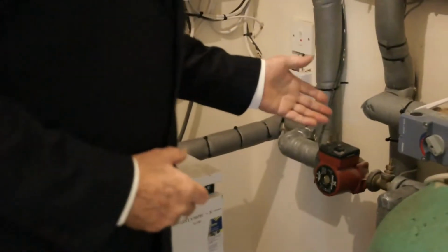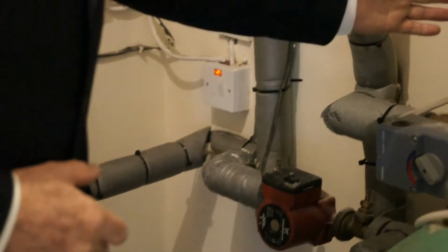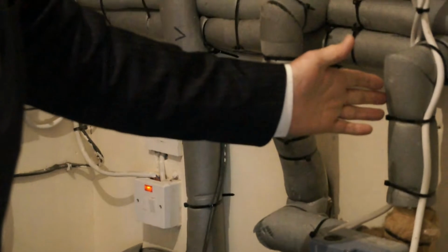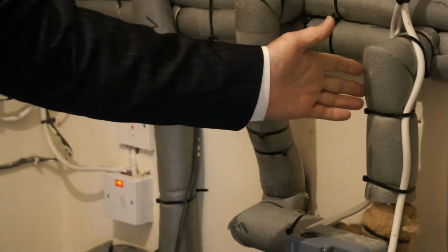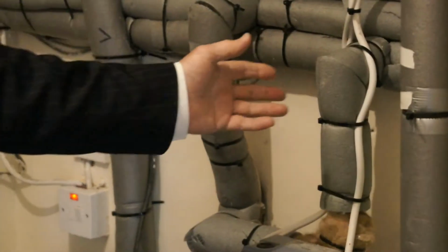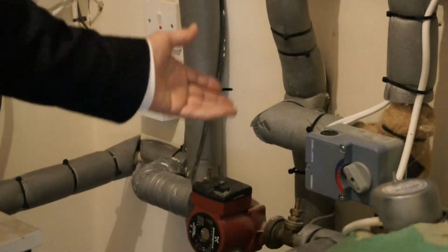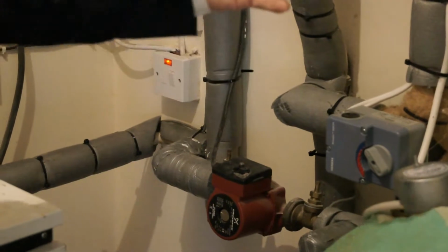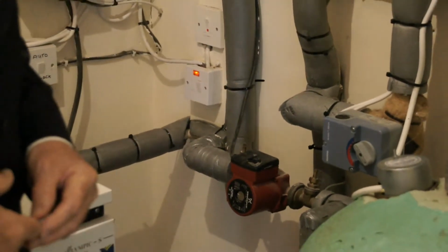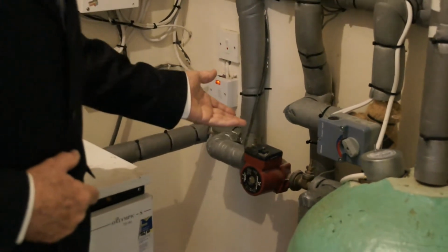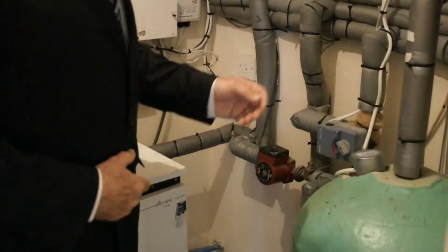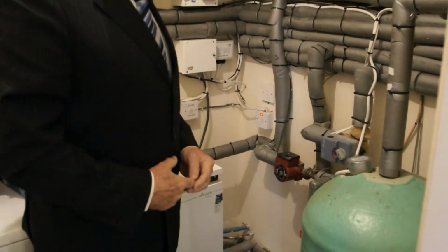So why is that? That's because the type of heating system that we have are fan convector heaters. If you run water at 75 degrees through them, and then when the thermostat cuts off there is no hot water going through, you get this wild fluctuation between hot air and cold air coming out of the fan-assisted radiator.